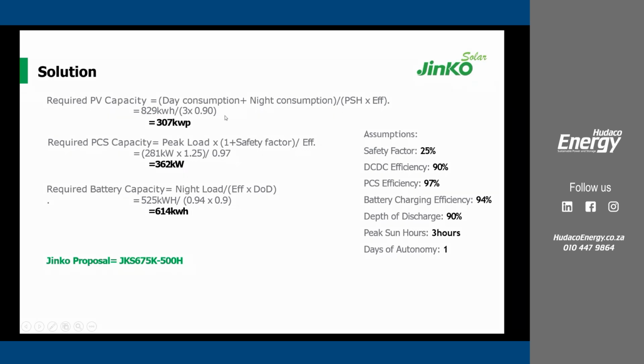Knowing the daily energy consumption, we can calculate the PV capacity, divided by the peak sun hours and also the efficiency, that is the DC-DC charging efficiency. You can see this is just basic calculations to roughly and quickly do your estimation. It comes to around 307 kilowatt peak. Then, of course, we need to determine the PCS capacity as well. We need to know the peak load, because the sizing of the PCS usually depends on the peak load.